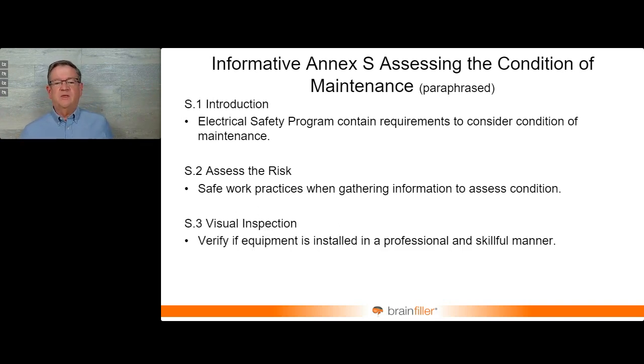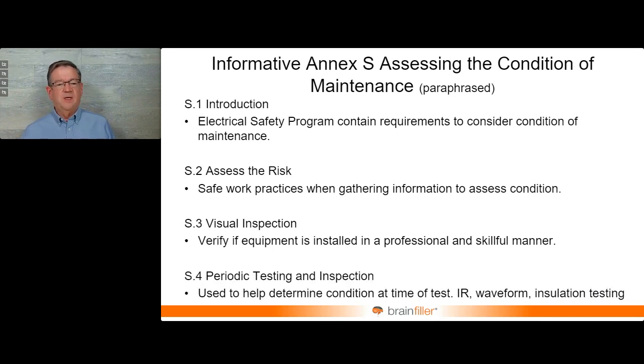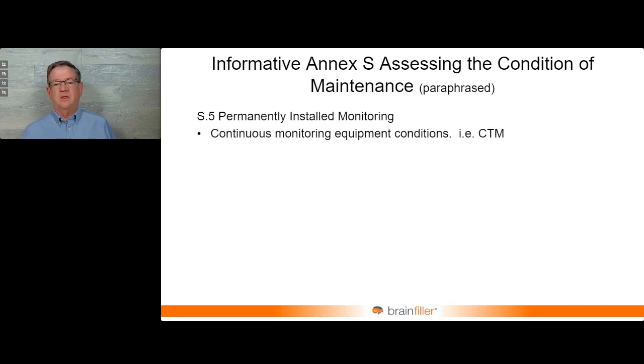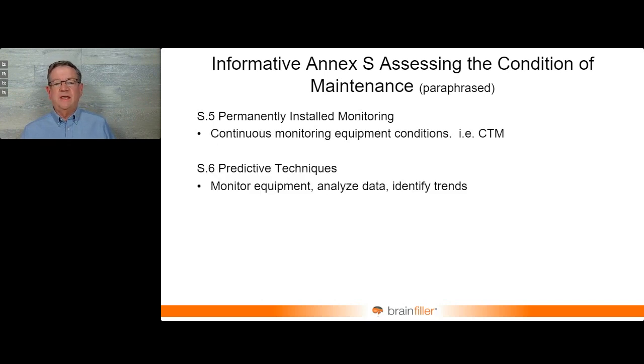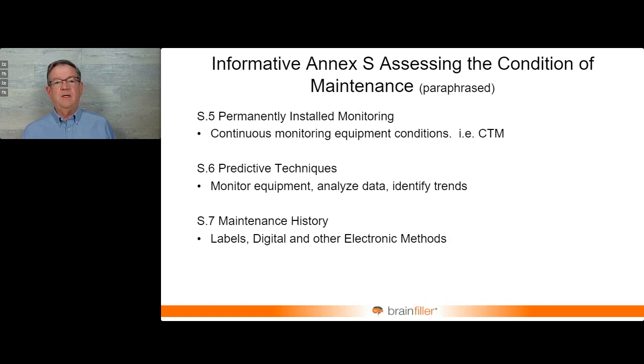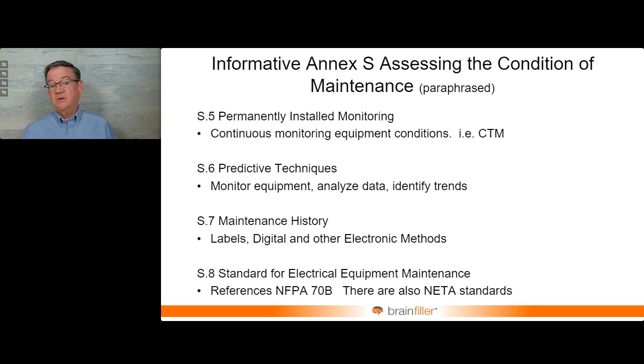And verify the equipment's installed in a professional manner. And you can use testing and inspection to help with the condition of maintenance. And there's also continuous monitoring that can be used. Monitor the equipment, analyze the data, identify trends, use labels for the maintenance history or some other form of documentation. And there are standards for the condition of maintenance. Of course, NFPA references another NFPA standard, 70B, but there are also NETA standards about maintenance.